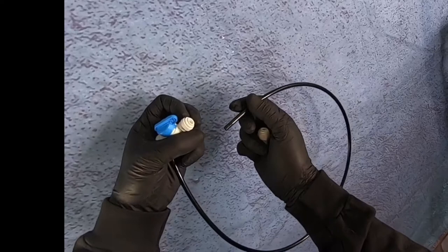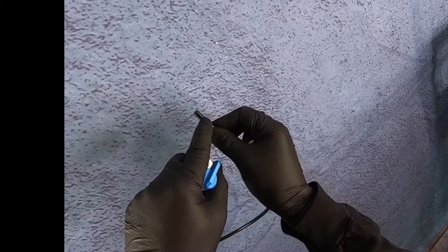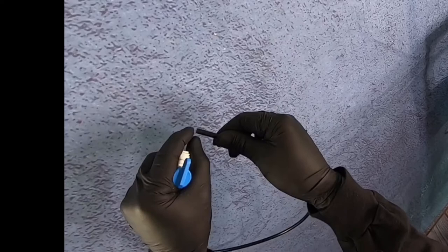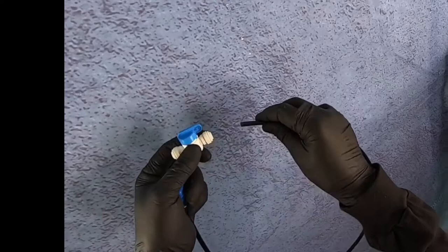And you'll notice when I take this out, there's a little bit of markings on here that the collar grabbed. And if you're going to reuse this piece of tubing, you could cut off just even an eighth of an inch, and it would seat in a new place inside the fitting. That would be nice, and definitely it's not going to leak or weep on you.